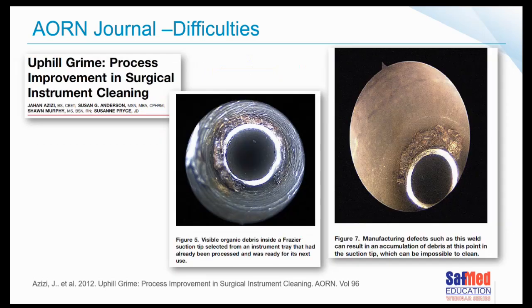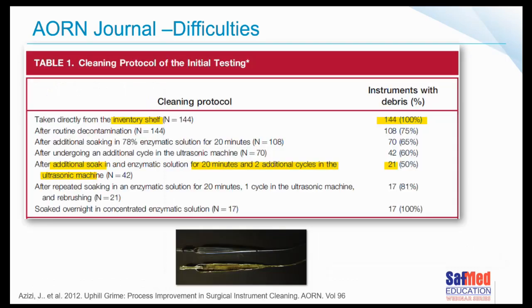Yeah, some of the images that they had. The one on the left is organic debris found inside a Frazier sucker. The one on the right is manufacturing defects, where the welding was not smooth on the inside, which you can't see, and ended up with this accumulation of debris in the suctions. So of the 144 instruments, after routine cleaning they found that 108 of them were not clean. So 108 of them still had debris in them.